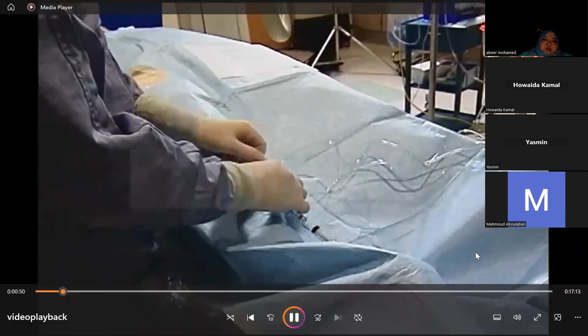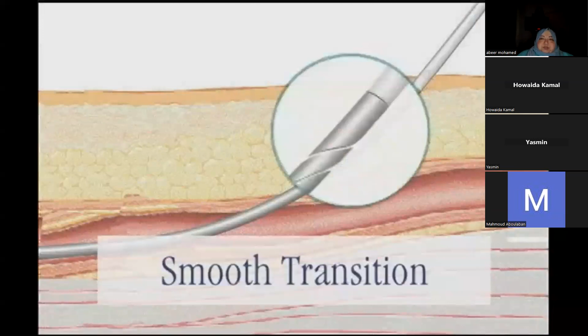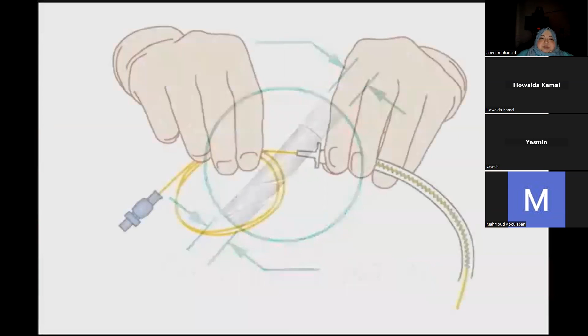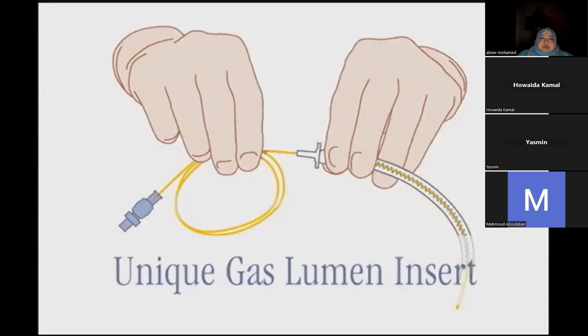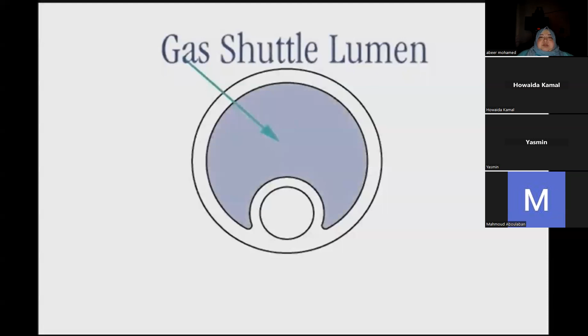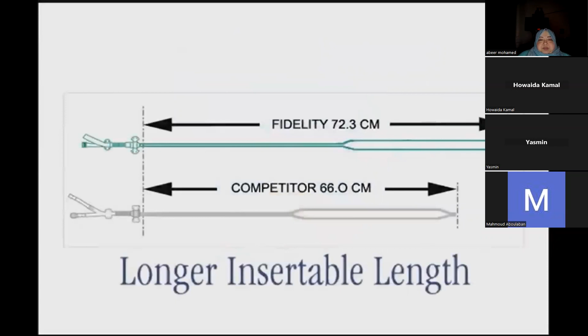This videotape reviews the insertion and removal of Datascope intra-aortic balloon catheters using both the sheathless and sheathed approach. The key attributes of Datascope IAB catheters are smooth transition between wrapped balloon and catheter shaft, a unique GLI or gas lumen insert allows a flexible catheter design and helps prevent kinking during insertion. The co-lumen design maximizes space for gas shuttle and pressure lumens. Longer insertable length than most IAB catheters.